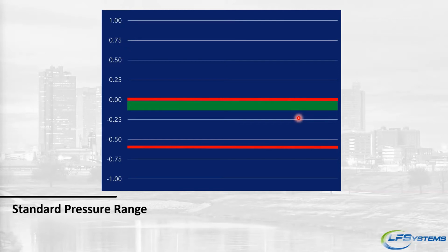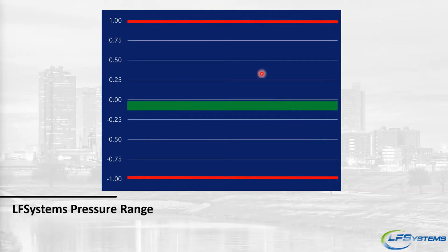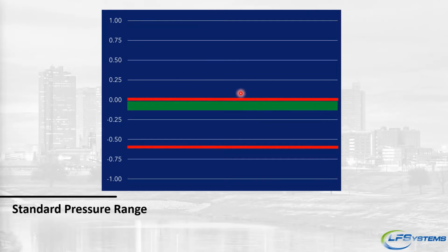The whole purpose of having a variable speed system is to minimize that excess air being drawn through. So we want to get it as close to 0 as possible. So again, maybe a 0.02, a 0.05, somewhere in that range, and just keep a very, very slight negative in the system. And that's why with ours, having that range on both sides really helps with that. Because again, if we set it here and the system dryers start to operate and the pressure starts to build, we actually can sense that pressure change and get us back to set point. With a negative only, if we start to climb above neutral, the controller actually doesn't see it.